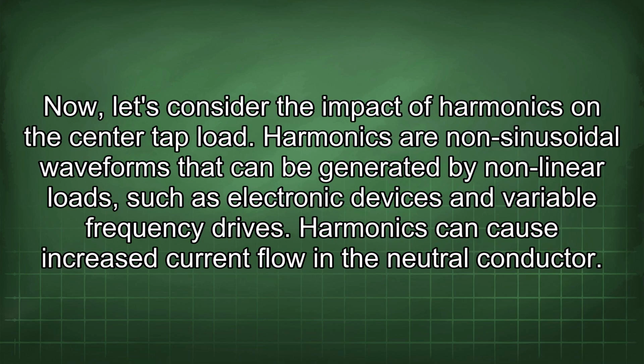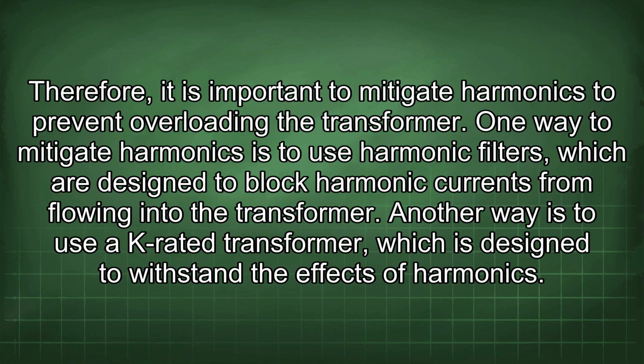Now, let's consider the impact of harmonics on the center tap load. Harmonics are non-sinusoidal waveforms that can be generated by nonlinear loads such as electronic devices and variable frequency drives. Harmonics can cause increased current flow in the neutral conductor. Therefore, it is important to mitigate harmonics to prevent overloading the transformer. One way to mitigate harmonics is to use harmonic filters, which are designed to block harmonic currents from flowing into the transformer. Another way is to use a K-rated transformer, which is designed to withstand the effects of harmonics.